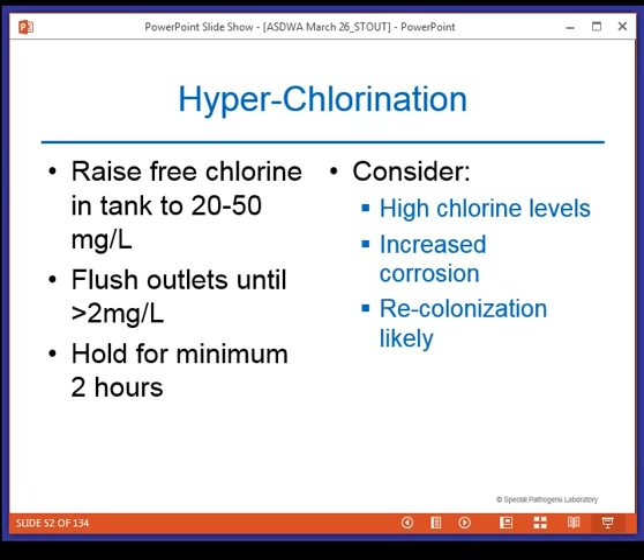When you do a shock chlorination, you take it up very high, 20 to 50 parts per million. You flush the outlets, making sure there's at least 2 milligrams per liter, then hold that for at least 2 hours—many people do it overnight. There are a lot of downsides: besides the high chlorine levels and associated disinfection byproducts, there's corrosion, and again, recolonization will occur after hyperchlorination.